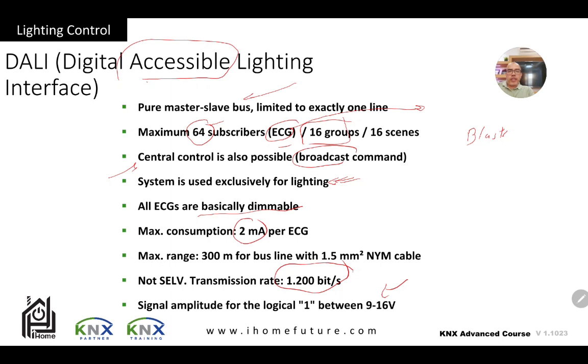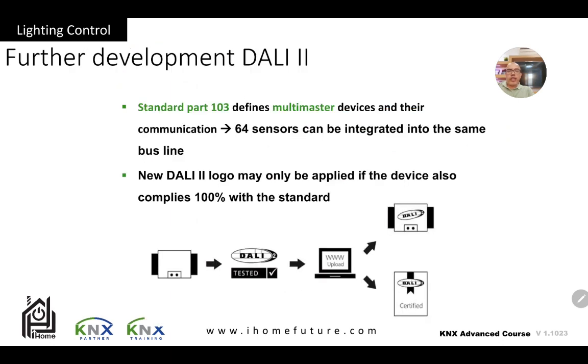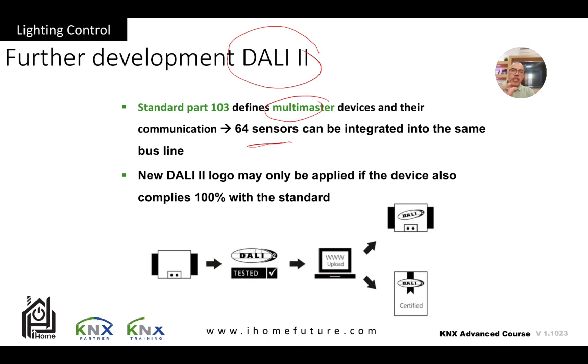DALI 2 is an improvement of DALI 1. It supports multi-master — it's no longer a pure master-slave installation. It still has 64 ballasts or ECGs and 16 groups, but now you can also add sensors or buttons to the DALI system, so it is not only for lighting anymore.